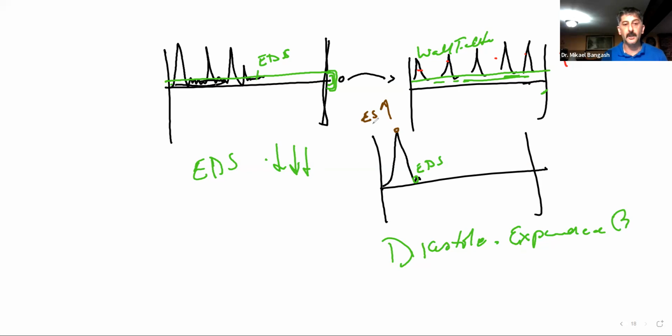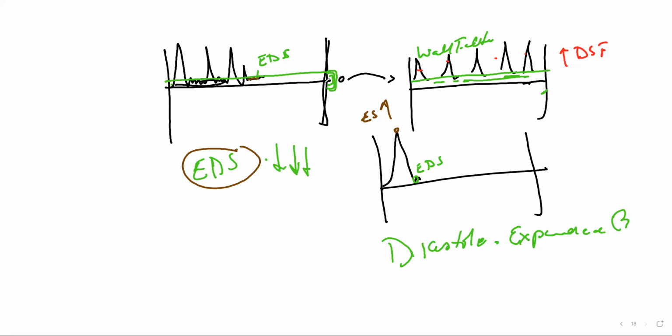So although not written in your book, please keep in mind that the wall filter may also filter your end diastolic velocities, if the end diastolic velocity is low enough to fall within the limits of your wall filter. Did that make sense? Yeah. Good.